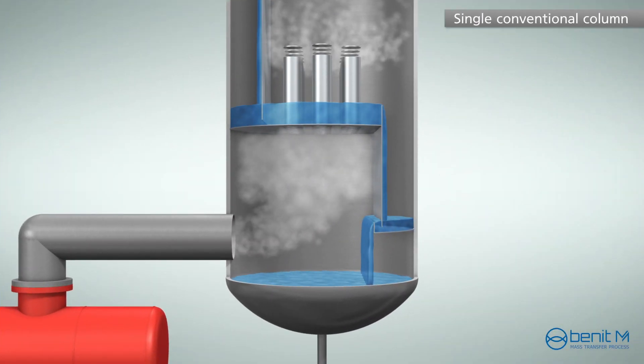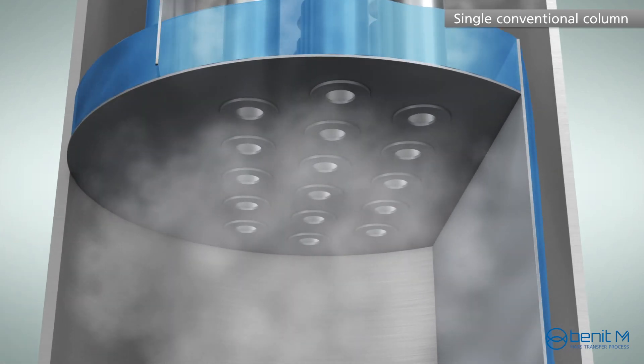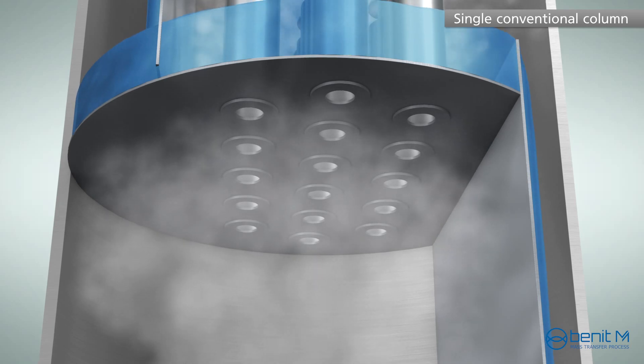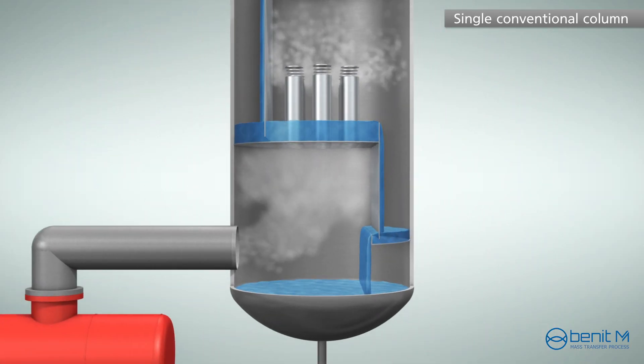Uniform vapor distribution is very important, especially in packed columns. It is recommended to design the chimney tray to have a proper pressure drop for even vapor distribution. In a chimney tray with a fixed open area, the developed vapor distribution might be acceptable at the designed vapor rate.